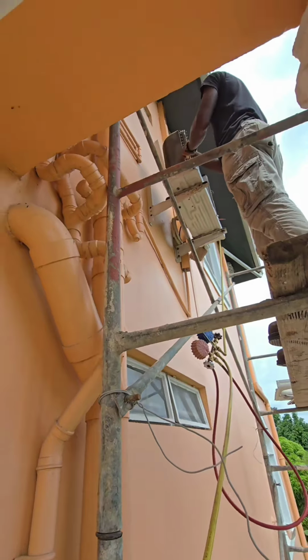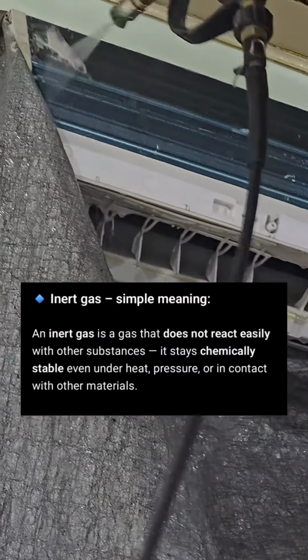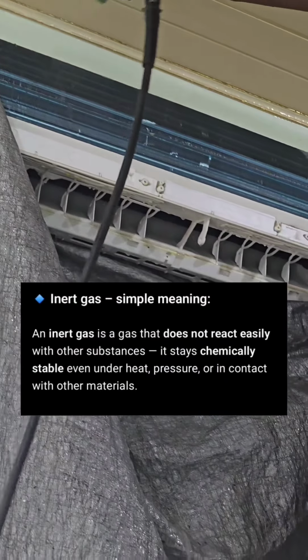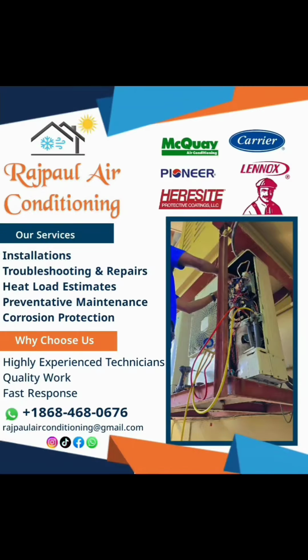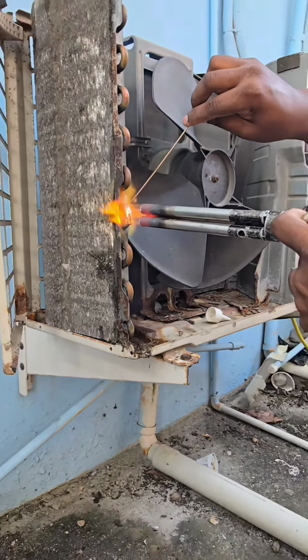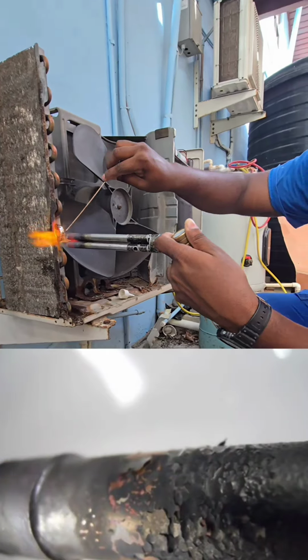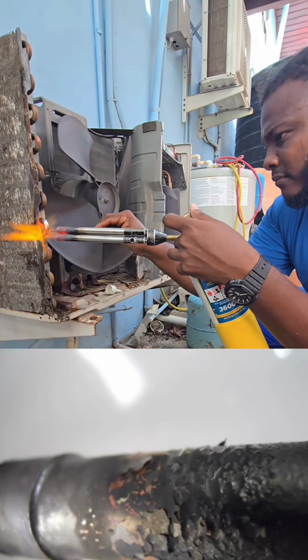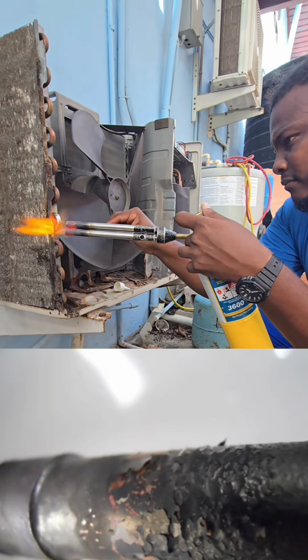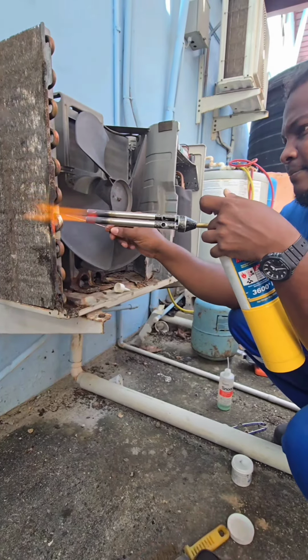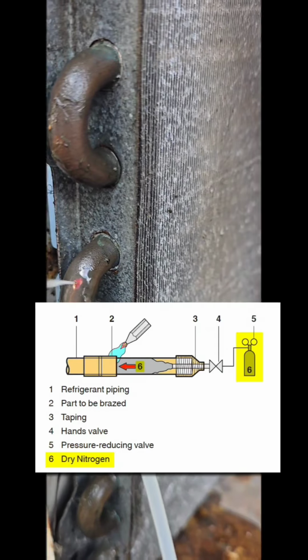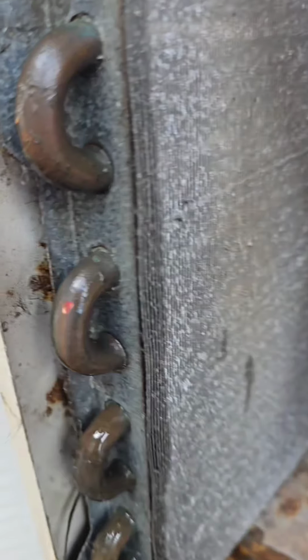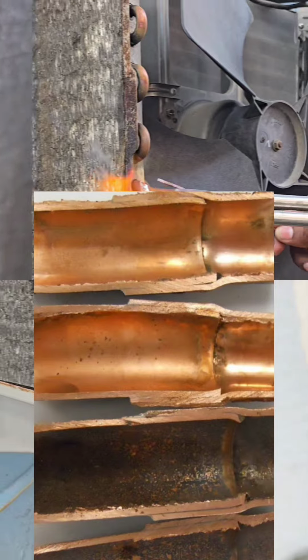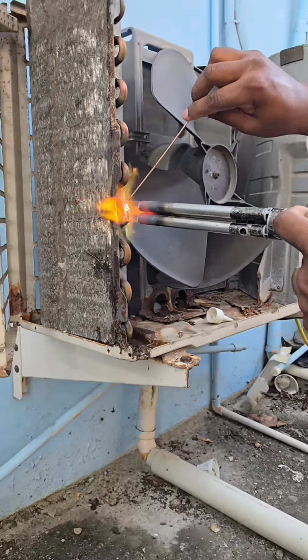So, for example, brazing, we use nitrogen because it's an inert gas. It is non-reactive and it keeps oxygen away. So the hot copper oxidizes quickly when met with oxygen, causing a black flake, almost like ashes. With nitrogen, you don't have any oxygen. It displaces the oxygen, so you don't get those flakes or that oxidization. And that's about the main reason in brazing for me.